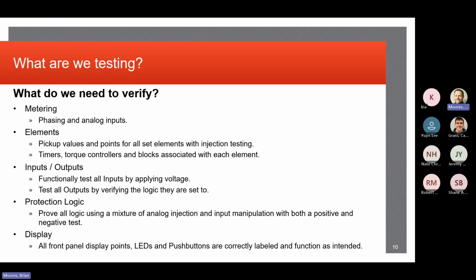Same with inputs, outputs. Once you verify the elements, now your inputs and outputs, you're going to make sure that those work. If you turn on an input with DC, you want to see that it turns on and the relay sees it. You want to see an output works when you toggle that output. And then you want to take those inputs and those outputs and make sure, as I mentioned before, you're looking at your logic diagrams. You turn on your inputs, your logic, you test your bits of logic, your ANDs, your ORs, your NORs, your NOTs, and then make sure you get the right outputs. And in this case, we're talking about physical outputs, not just gated outputs. A gated output could become, or your logic equation could drive a physical output.